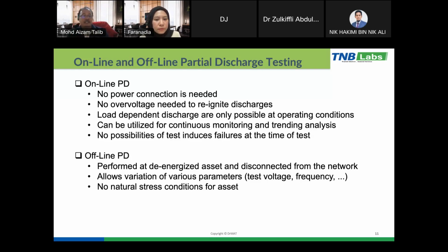And then through this online PD measurement, we can use it for continuous monitoring and trending analysis. So we can do the trending of the partial discharge activity from its inception until now, as it becomes bigger and bigger. But through this online measurement, we are not able to apply induced voltage. Sometimes we can do the destructive test to see whether the equipment is able to withstand the induced voltage.